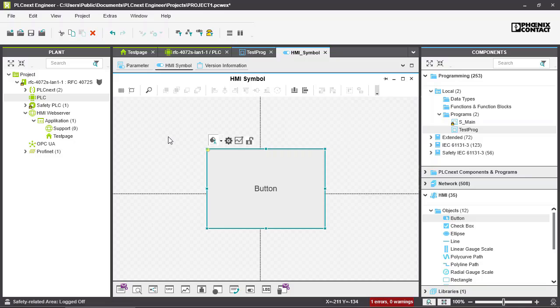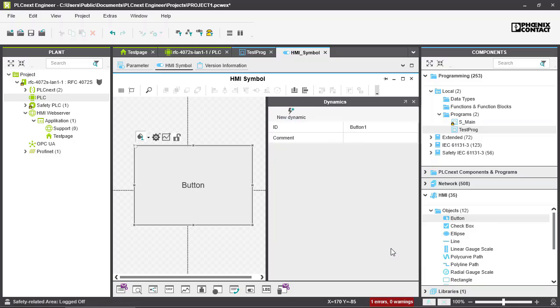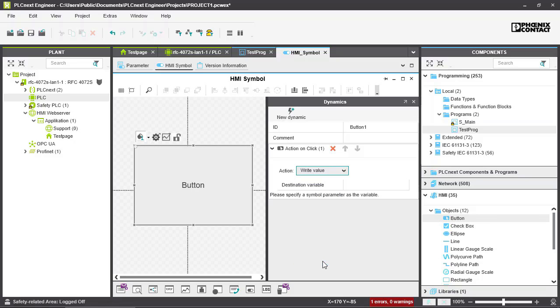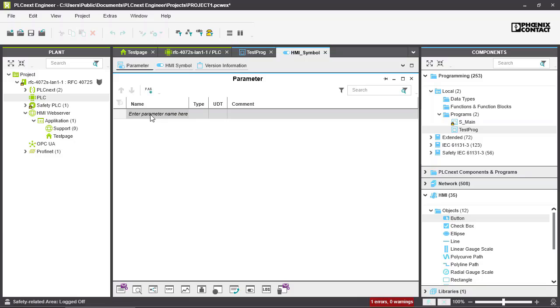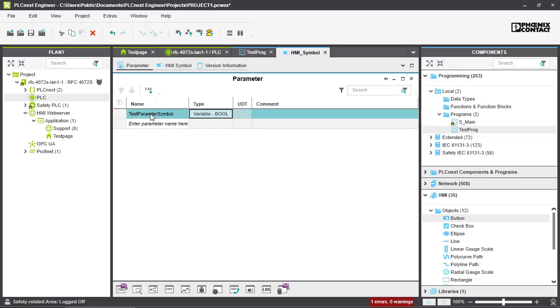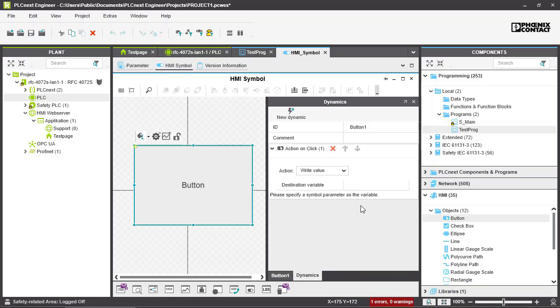Inside the symbol, we can add dynamics just as before — an action dynamic on click with 'write value'. However, when selecting a destination variable, you'll notice there is none available. This is because inside an HMI symbol we must first create parameters. We can create a test parameter — for example, 'symbol_variable' of type bool — and then in the button's dynamics we can select that parameter.